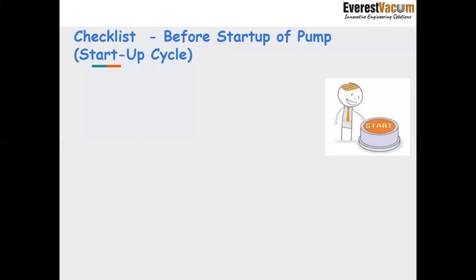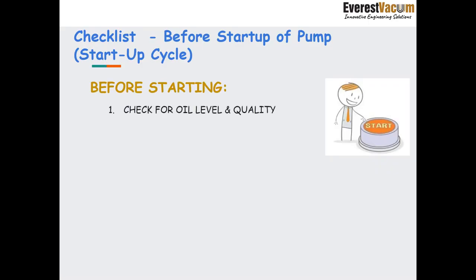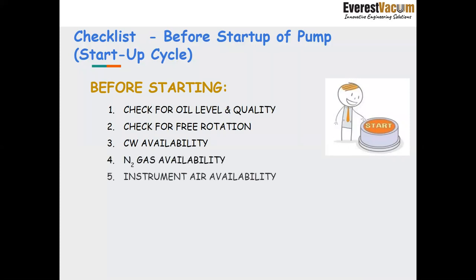So for the checklist before startup of the pump, what is the startup cycle which we are discussing? Before starting, we need to check the oil level and quality. We need to ensure that the pump rotates freely. There is the availability of cooling water, nitrogen, and instrument air. Thereafter, having availability of all these 5 points, we can start the pump.